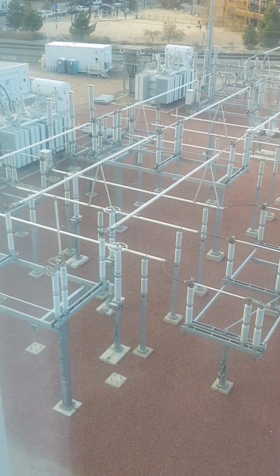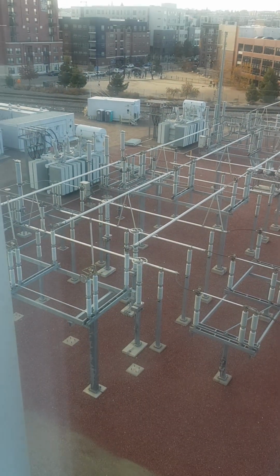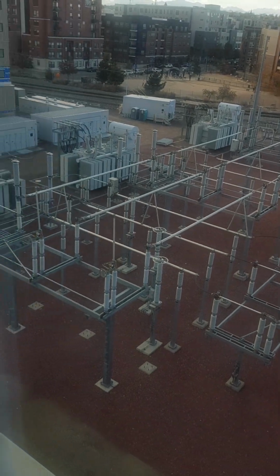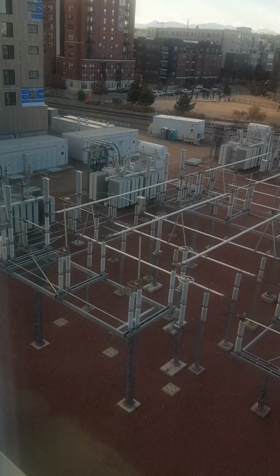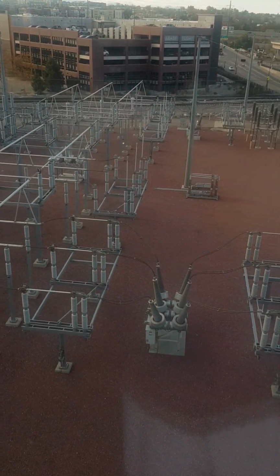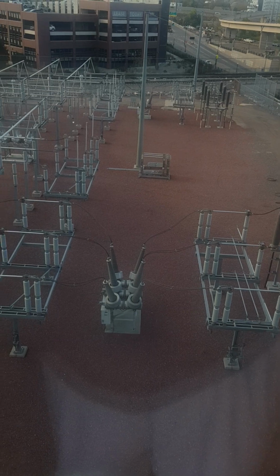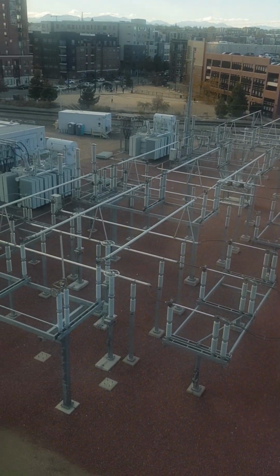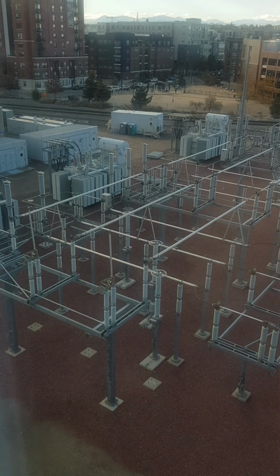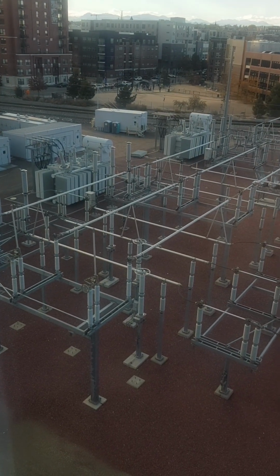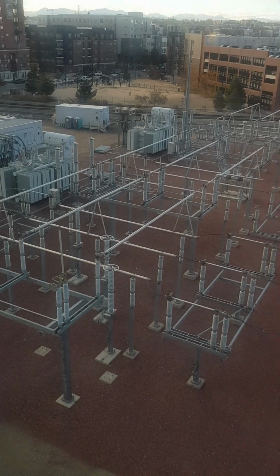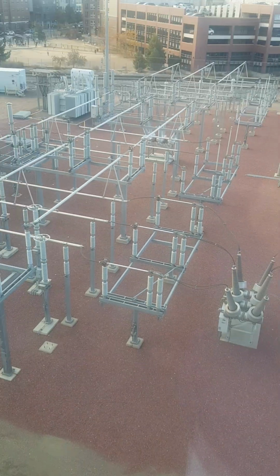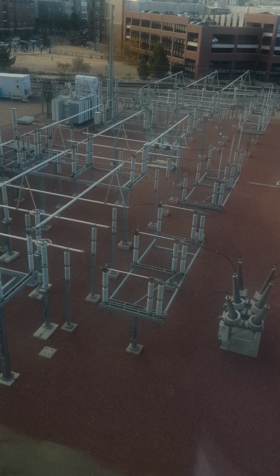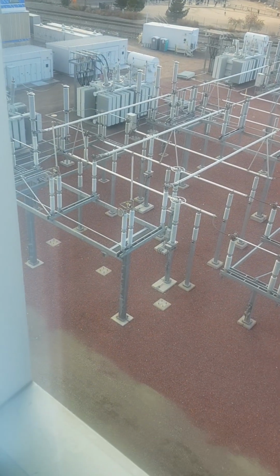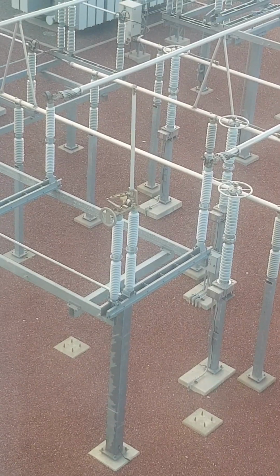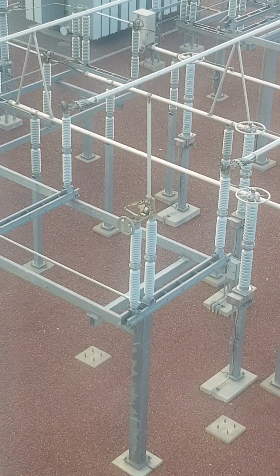Then we see this mesh of connectors. What is the objective of this? To explain this, you can see here at the back, there are three transformers, and almost everything is repeated. So basically, this substation has three parallel branches. Now, sometimes I need to connect one branch, two branches, or three branches together. So these disconnector switches are to connect and disconnect between the branches of the substation itself. You can see here, these switches currently are open. But of course, as I mentioned to you, there is no power connected to this substation.